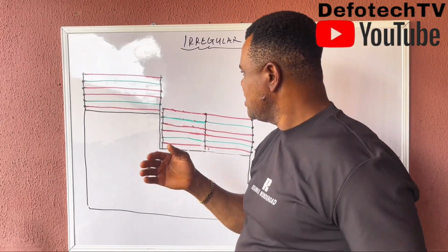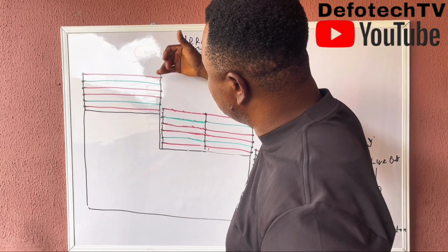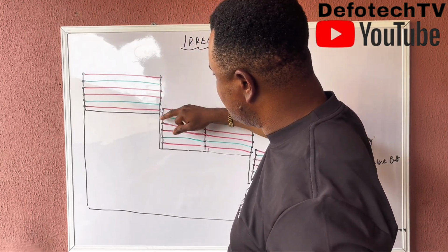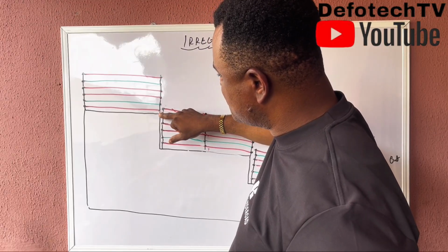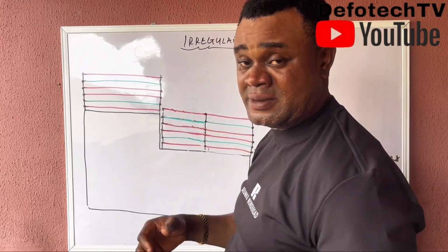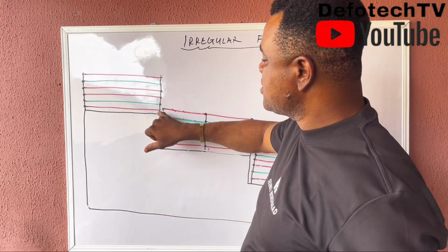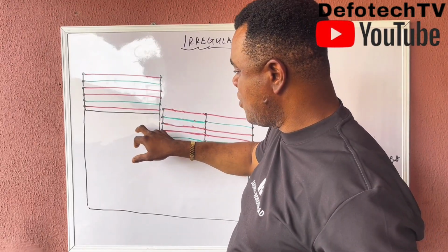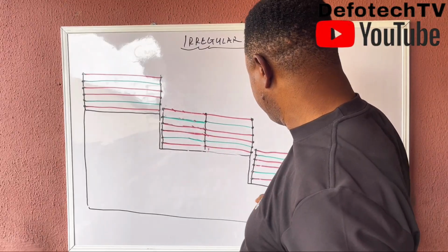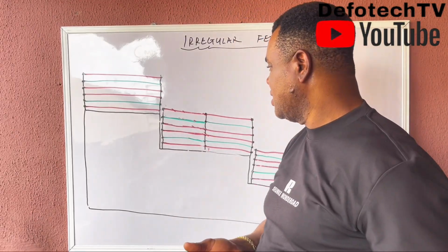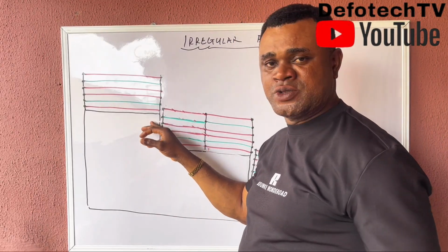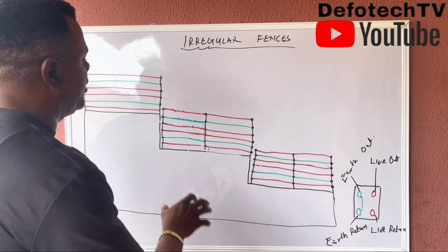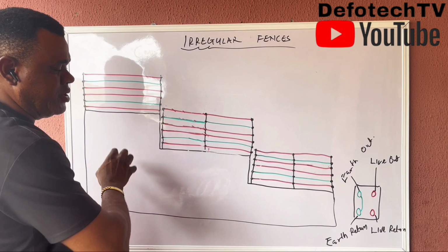They are there to take power from point A to point B, passing through areas where you may be afraid that if they touch, they can cause harm. But because they are insulated, if they touch this bracket or this fence, these walls, there is no contact because it's insulated. So if you're using HT cable, just know you must use HT cable in scenarios like this.